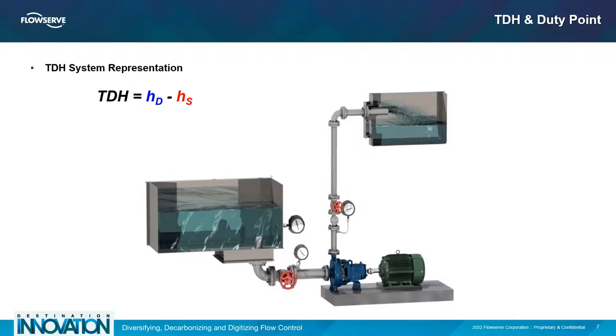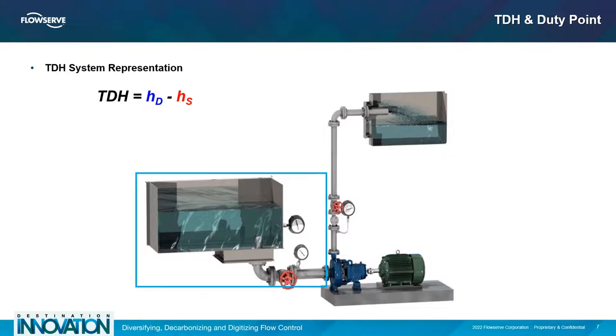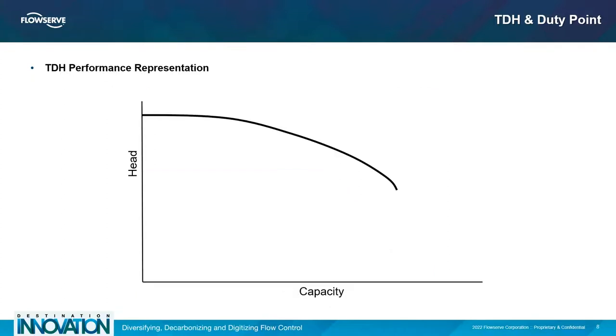Looking at a relatively simple system, the downstream portion highlighted will have a certain amount of pressure, frictional velocity, and elevation for the pump to overcome. Similarly, the upstream side will have a certain pressure, frictional velocity, and elevation to be endured by the pump. Subtracting the discharge components less the suction components will provide the TDH produced by the pump as seen by its characteristic performance curve. Here, five points of operation were chosen from pump shutoff to end of curve in order to provide a graphical representation of TDH.